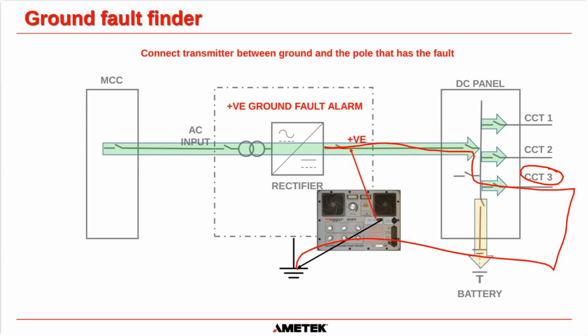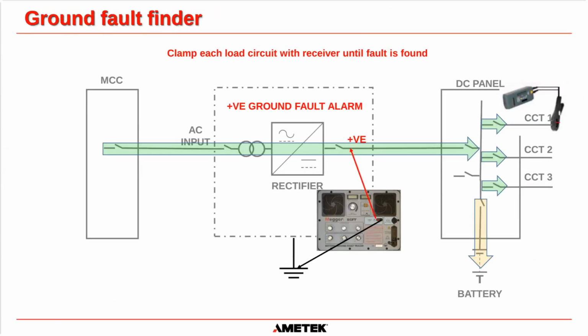That is what the ground fault tracer is doing. It's injecting a low voltage, low current AC signal. It shouldn't cause any spurious trips on any of your circuits. You can do this test live, okay, without switching any of the breakers off. And then, once you've connected the positive and negative to ground on the signal generator part of the BGFT, you have a receiver part of the BGFT as well. And it's got an amp clamp, basically a CT, that is tuned to listen for that specific frequency signal that's coming from the BGFT.